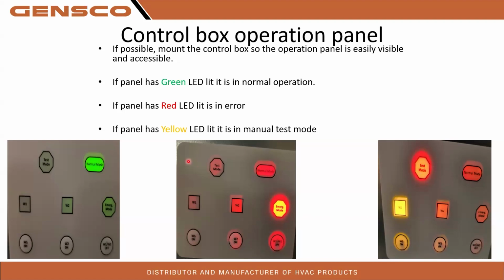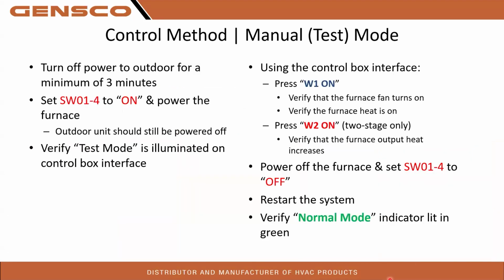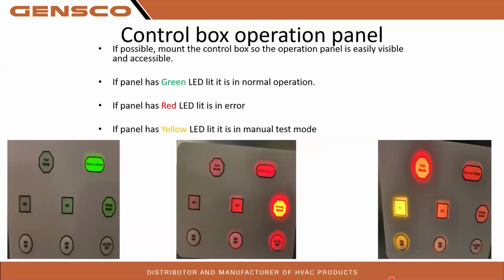Test mode. If you have a yellow LED lit right here in your W1 test mode, that means you're in test mode. SW01 switch 4 is on, and you're able to run that system using W1, W2, which I actually have coming up right here. So in order to use that test mode, you're going to power off the heat pump and the furnace for at least 3 minutes. That way it has time for everything to bleed down capacitor-wise. You're going to set SW01 switch 4 to the on position, and then power the furnace only. So this is if you guys are wanting to test the gas furnace to make sure that the gas is actually working. Once you power the furnace back on, this panel here should light up and you should see the test mode LED lit up.